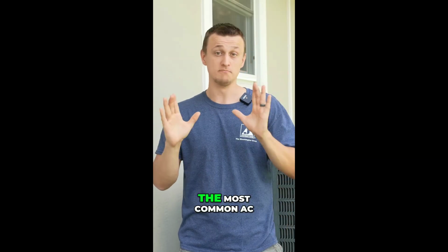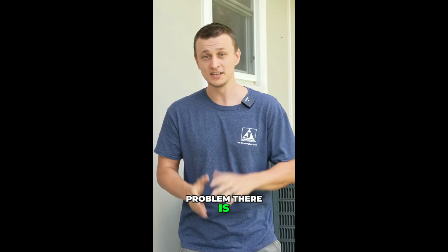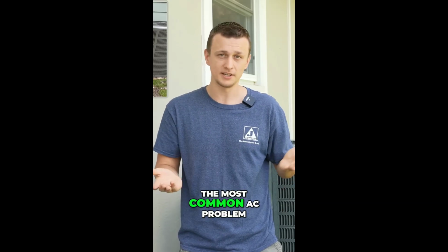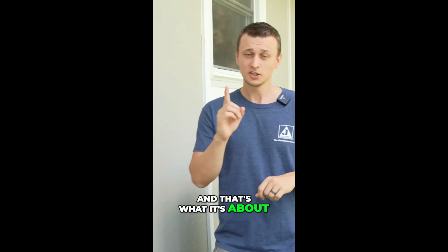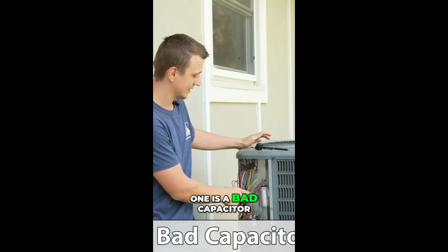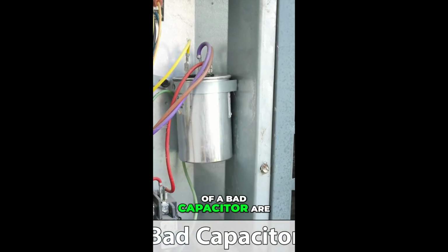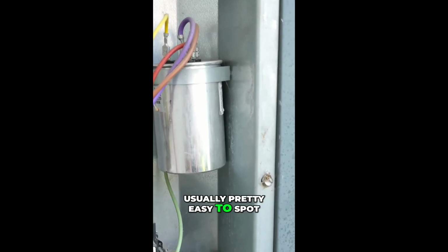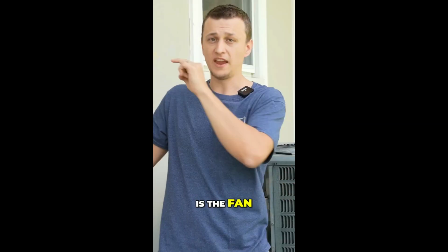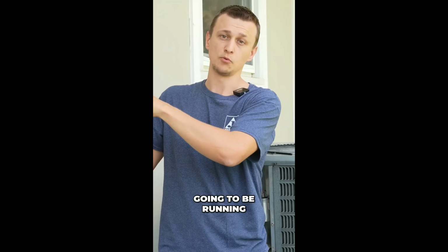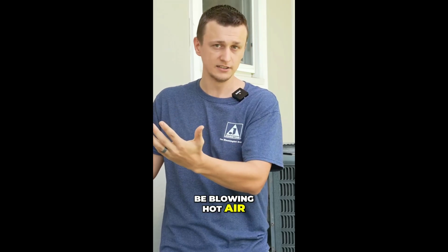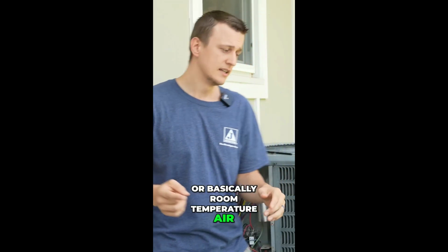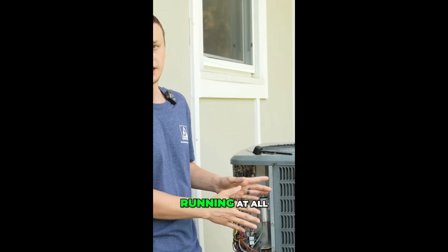Problem number 1. This is by far the most common AC problem there is. In fact, I even have a video called The Most Common AC Problem, and that's what it's about. Problem number 1 is a bad capacitor. The symptoms of a bad capacitor are usually pretty easy to spot. What will happen is the fan inside the house is going to be running, but it's going to be blowing hot air, or basically room temperature air, and the unit outside will not be running at all.